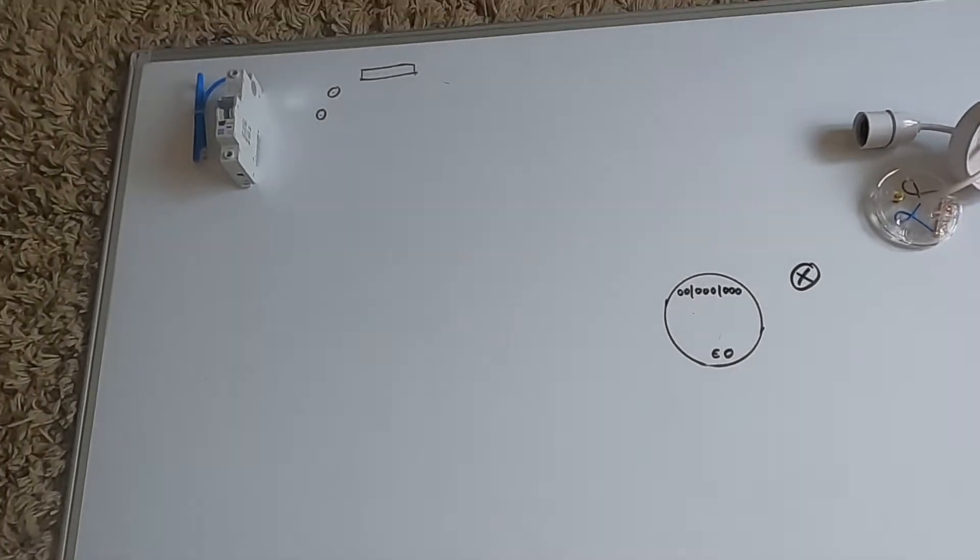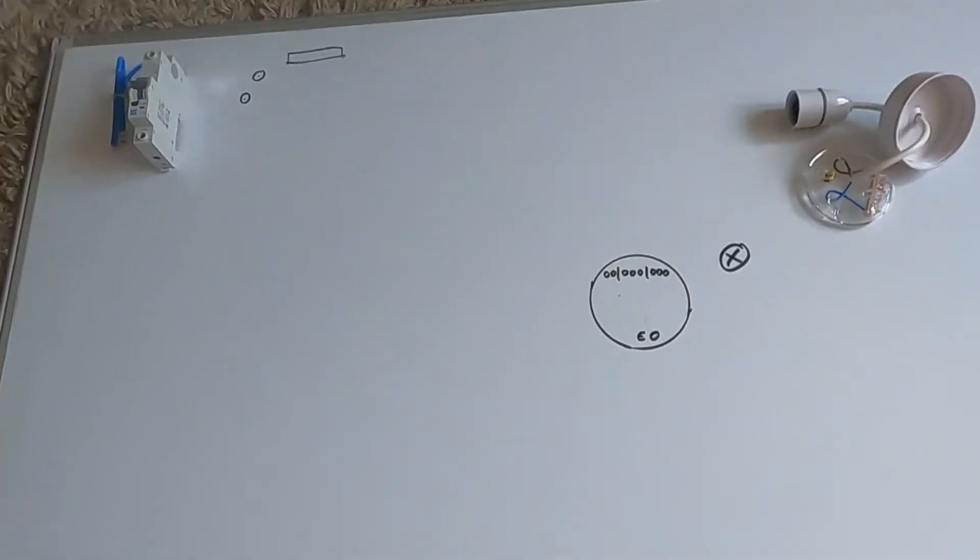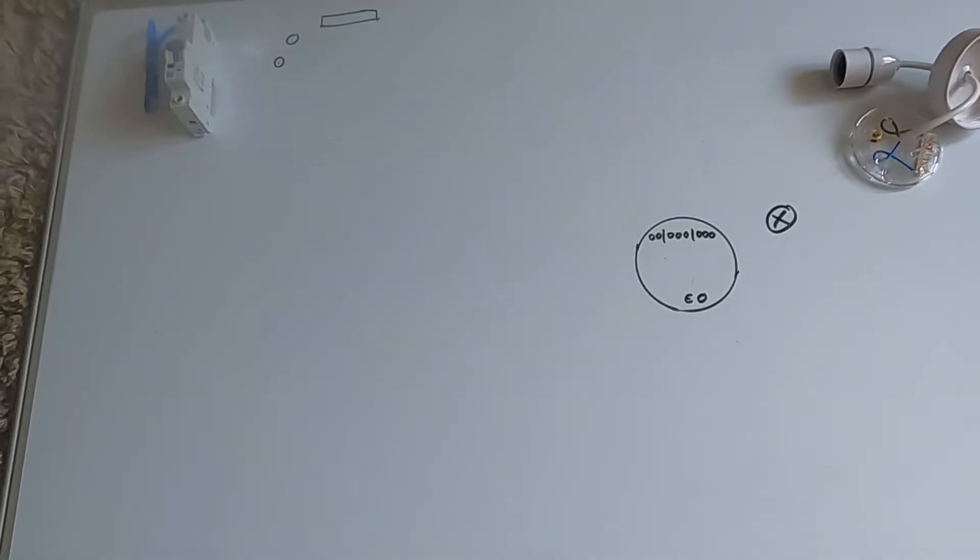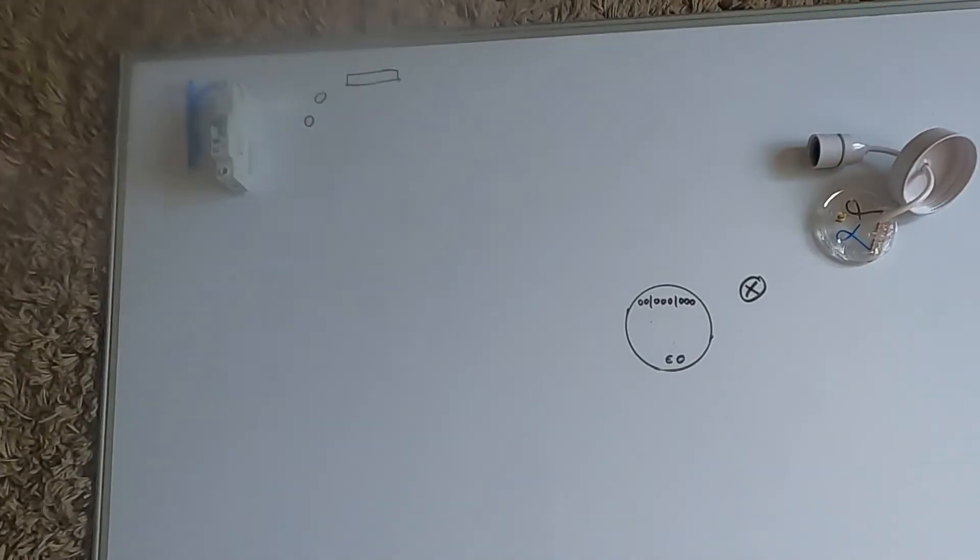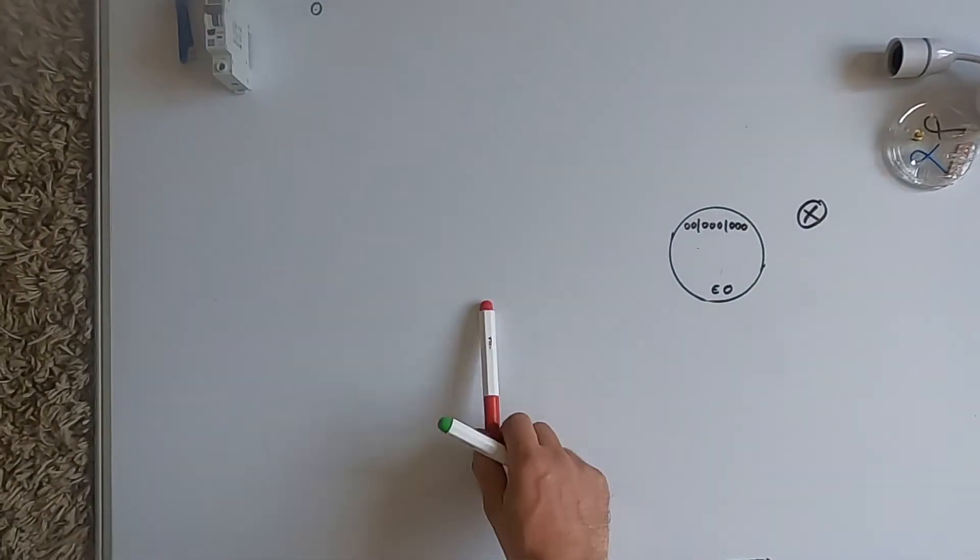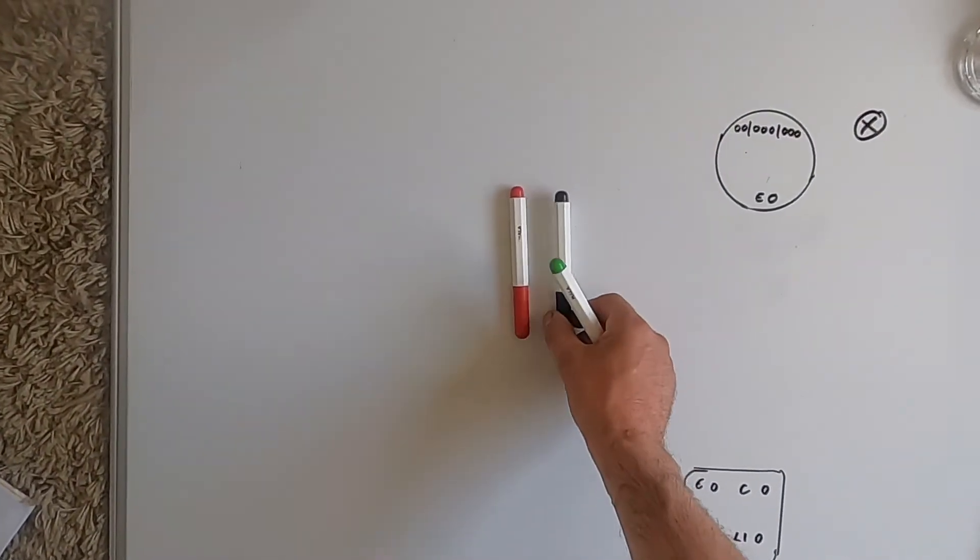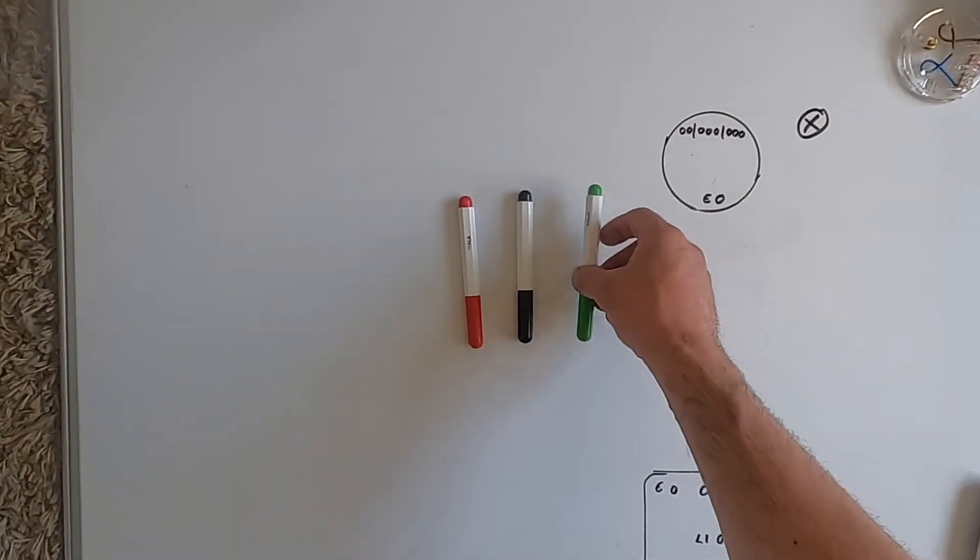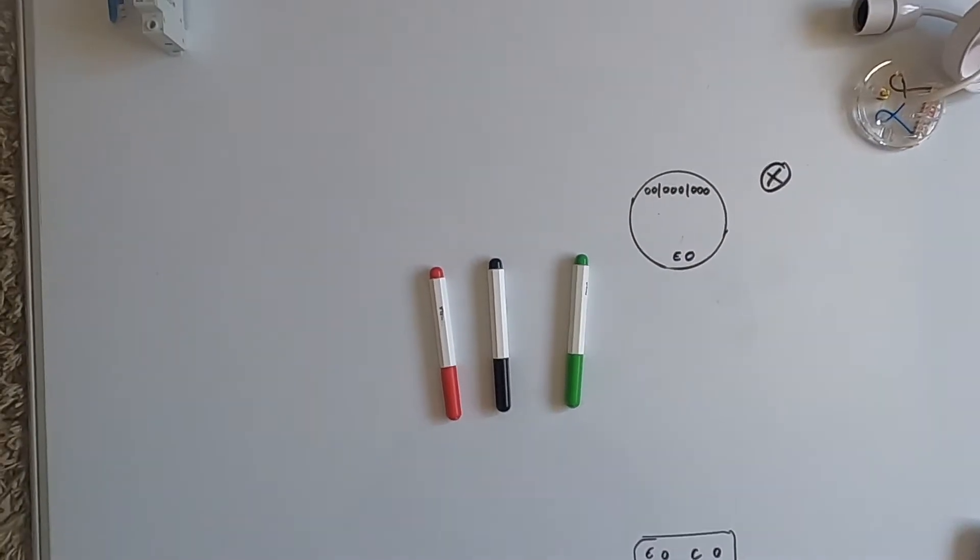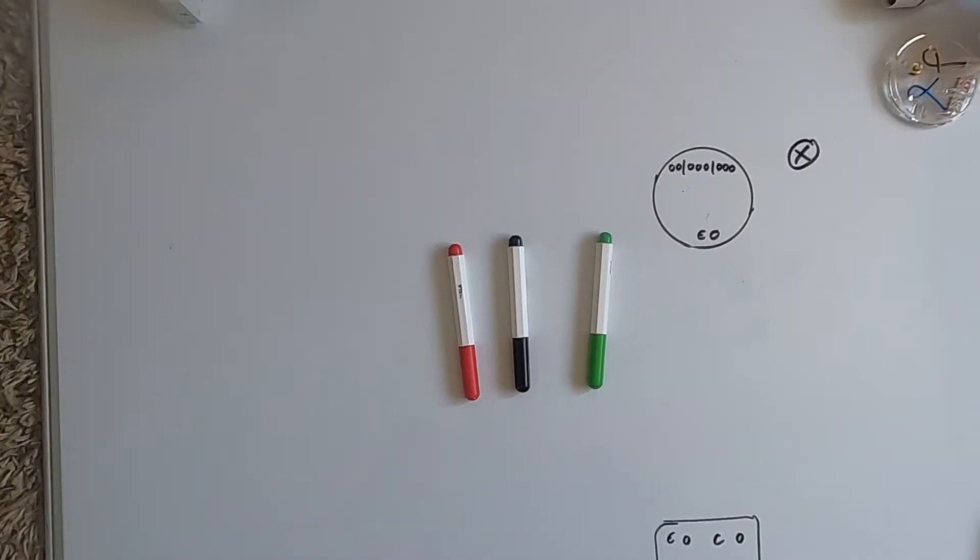And because this is going to be a traditional way of maybe old houses built prior to 2004 before the colors got harmonized, you'll find that the live is red, the black will be neutral, and the earth will be green and yellow. So these are the colors we're going to use.